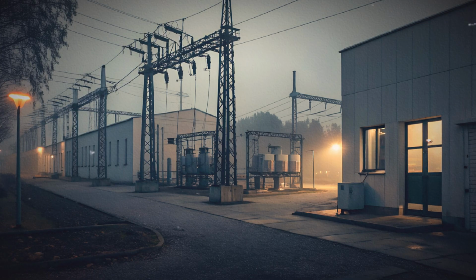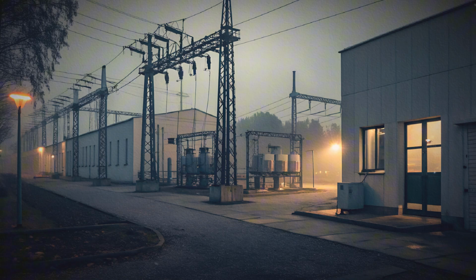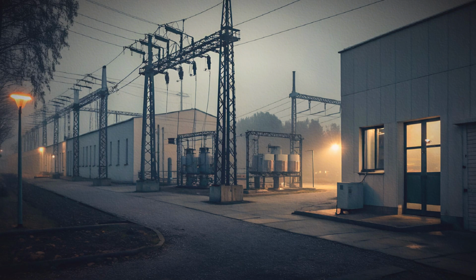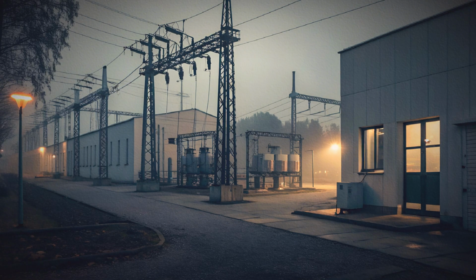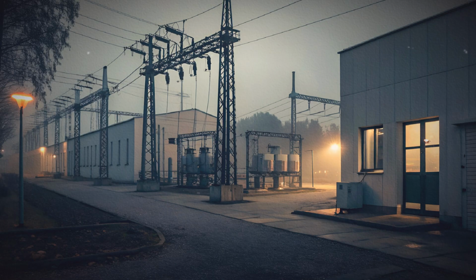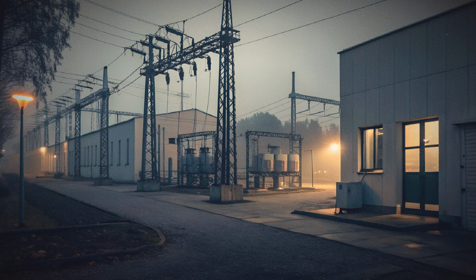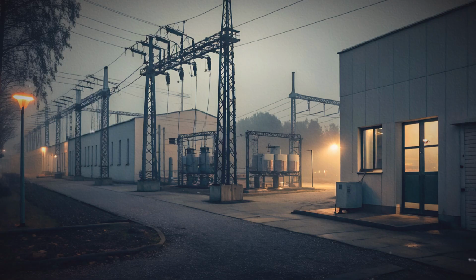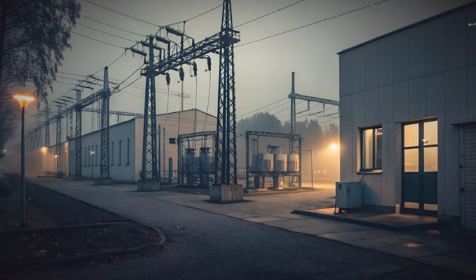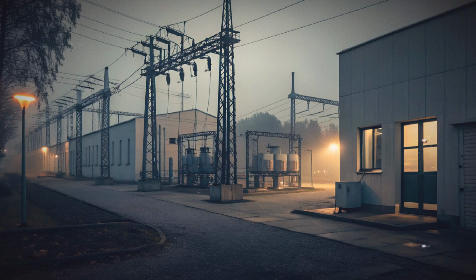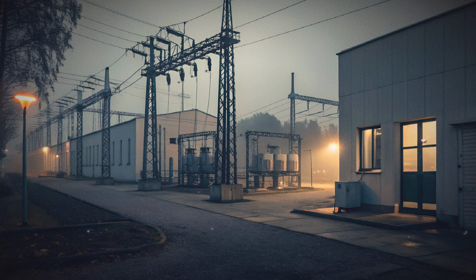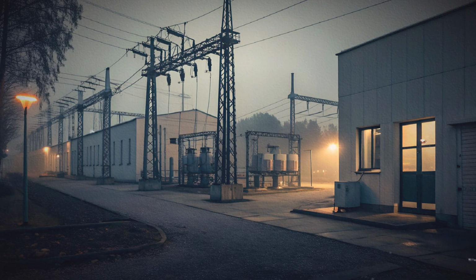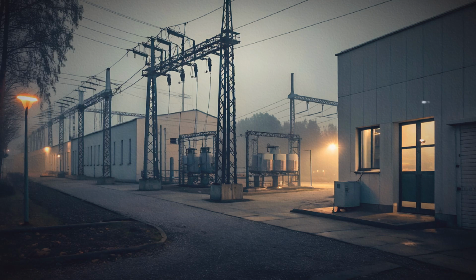Reactive power, which is distinct from the real power consumed by loads, affects voltage levels along the network. Capacitor banks supply reactive power locally. Reactors absorb reactive power when necessary. Some substations include synchronous condensers or static compensators for dynamic control. These devices help stabilize voltage during changes in load or line conditions. Managing reactive power reduces voltage drop over distance and improves the ability of the network to deliver usable power.